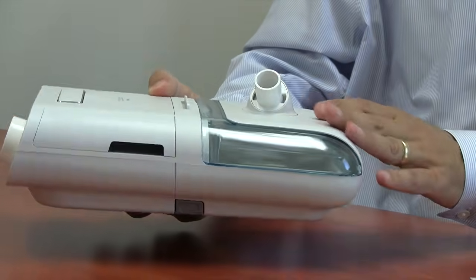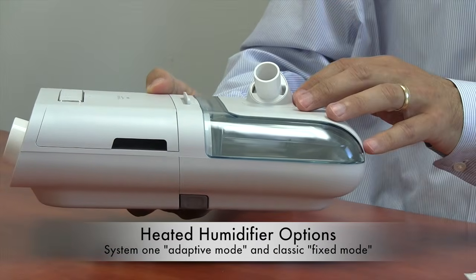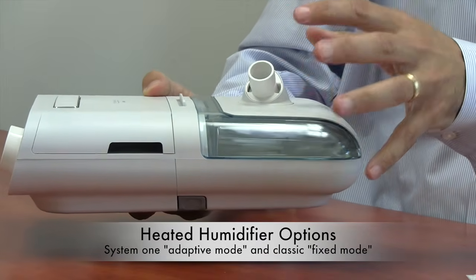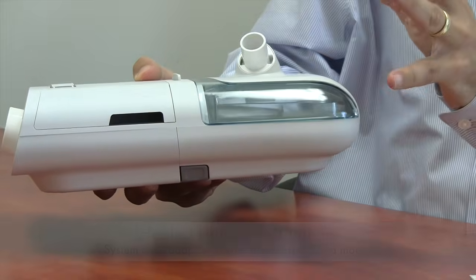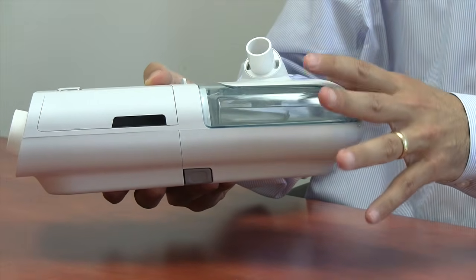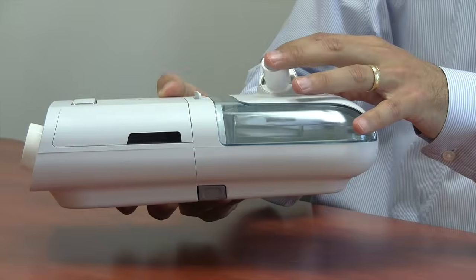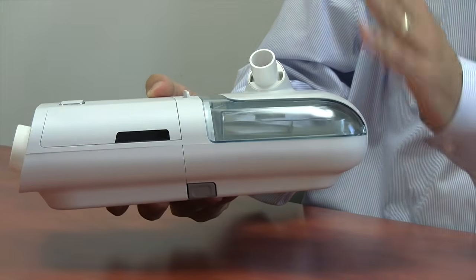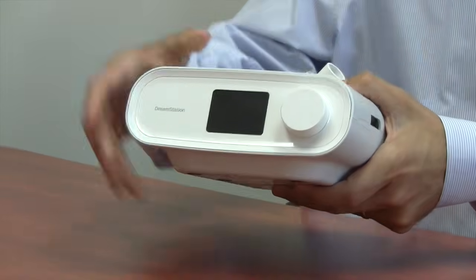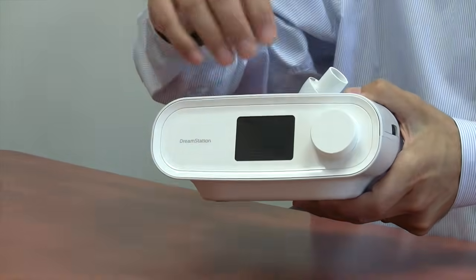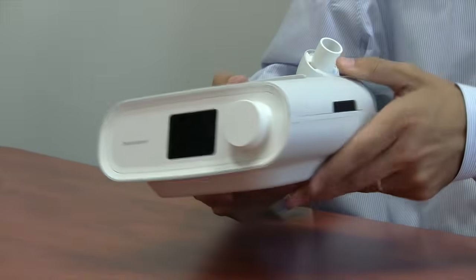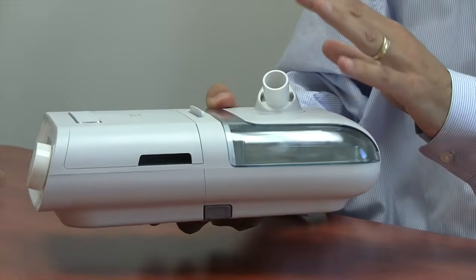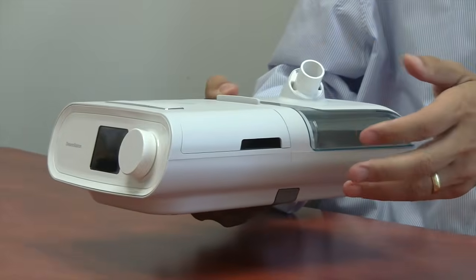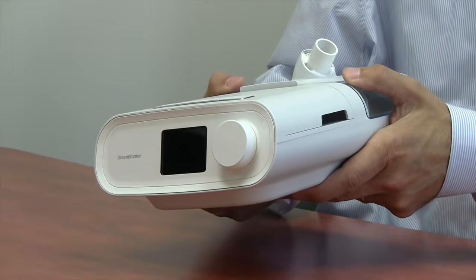So, some humidifier changes. This has something called adaptive mode. The heated humidifier and the heated tube are going to monitor and know what your room temperature is and set themselves automatically. There's also a classic mode where you can override that, and through this toggle here you can set it to whatever you'd like. So you can either use the automatic mode, which is very, very effective, or you can override it and change it to whatever temperature you'd like.